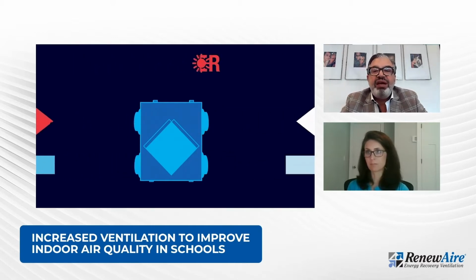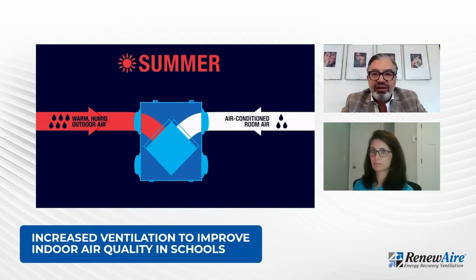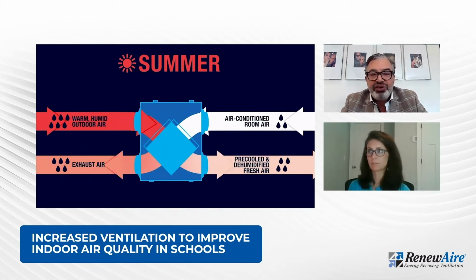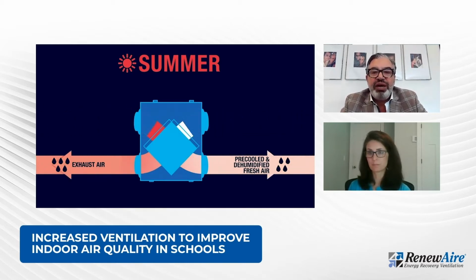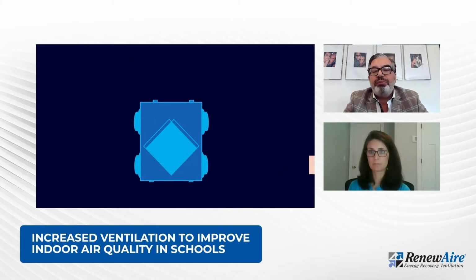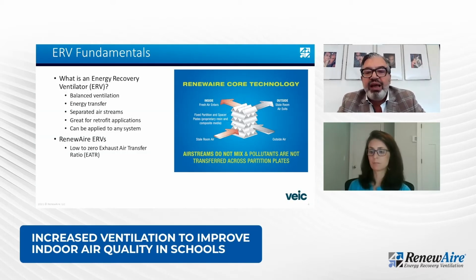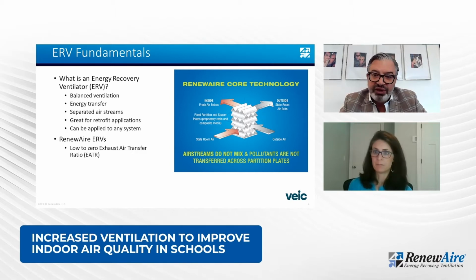So we have two fans operating in concert with each other, one exhausting the air and one bringing in the outdoor air. Now, that energy transfer occurs through a core that looks like a cardboard box, as you see depicted on the screen there. What's interesting is that you take the exhaust air from the room and put it across one side of that energy recovery core, where we're transferring both the sensible and the latent energy.